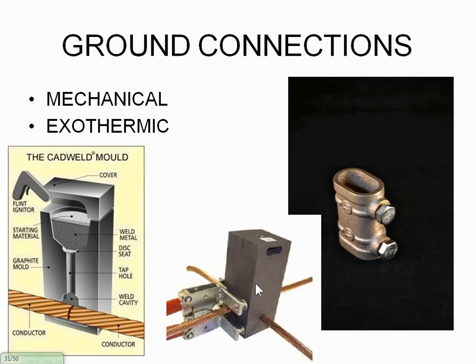And these are the different ways that you can connect to it. Typically, what we do is only mechanical or exothermic. This is how we attach to a ground rod. It's obviously a UL listed product that our company creates. This is exothermic welds, which I don't know if you guys are familiar with. Thermal Weld makes a lot of them, Erico, pretty much the big electrical companies actually make these. What they do is you just take the cable, put it together, you drop your weld mold in there, and what they have is a little bit of gunpowder on the top of it. You spark it up, the weld metal melts, basically fusing together the cable. It's just another way to secure the lightning protection. It's either welding or mechanical. It's pretty typical. And all these methods, guys, are approved methods for grounding your system for electrical.